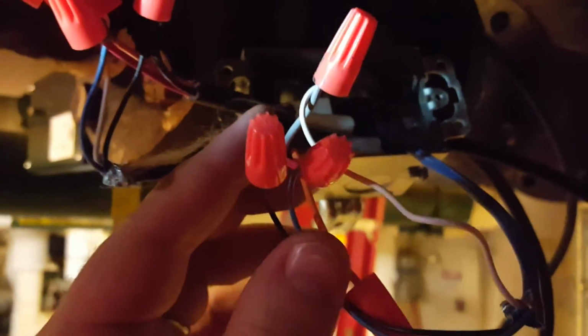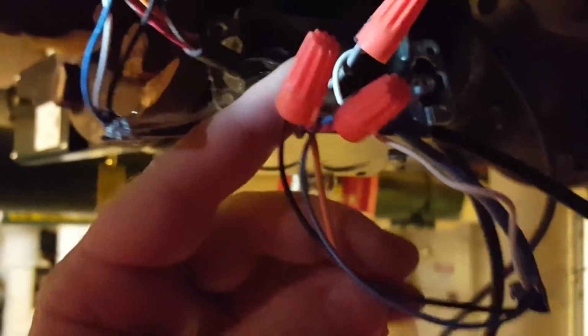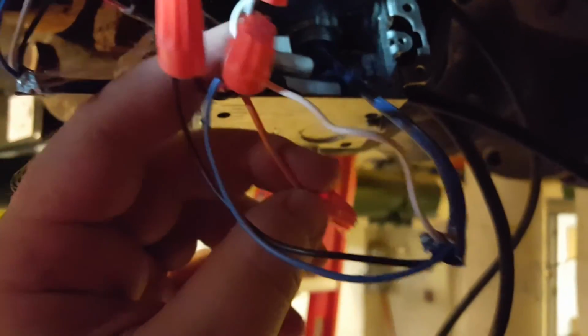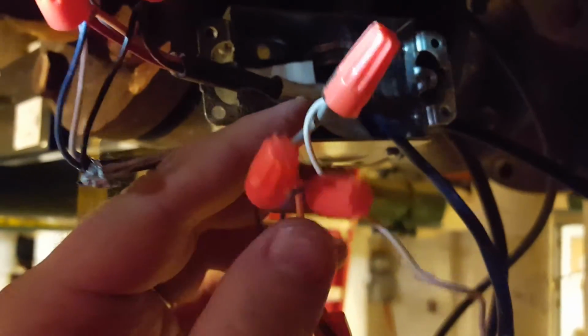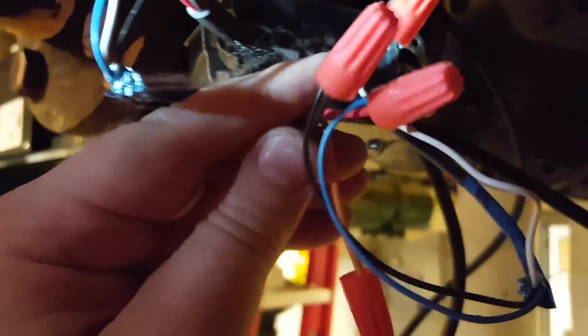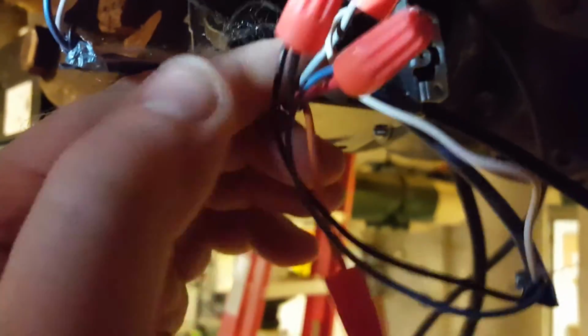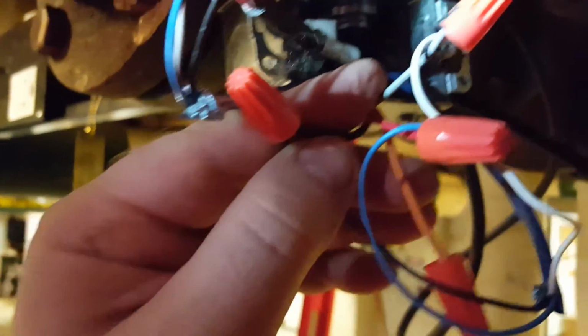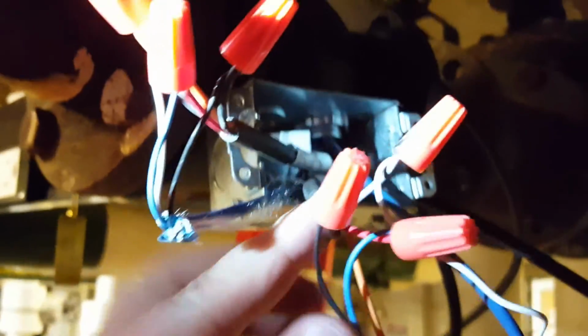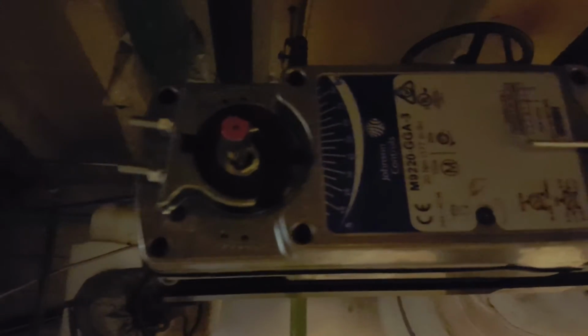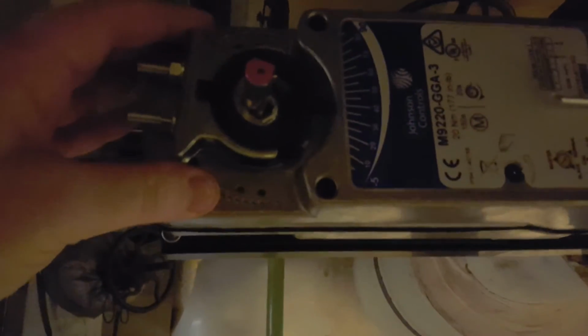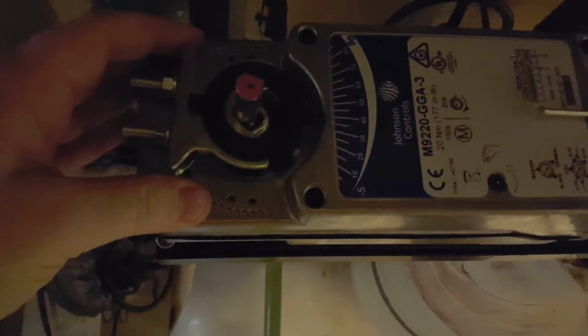And here we are at the valve itself. We have our hot wire, our positive 24 volts. We have our common wire that is both AC common as well as our analog output common. And then we have our signal wire, which is our 0 to 10 volts DC that will actually drive the valve. Once again, after everything is wired up, be sure to test the system.